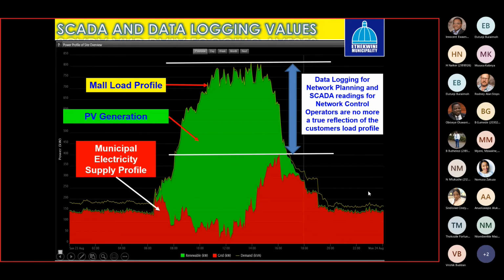Another problem is with our SCADA system — supervisory control and data acquisition — which our network control officers use to view real-time loading. With large PV systems, batteries, and other generation sources, they're not getting a true picture. Looking at a customer's PV system with its load profile, the control officer would typically only see the red part of the curve — the net loading fed back into the network — not the customer's full load. Even from a planning perspective, recording customer or network load profiles doesn't give a true reflection, because the PV or other generation system distorts the curve. This needs to be accounted for, as it could lead to incorrect planning and overloading of the networks.